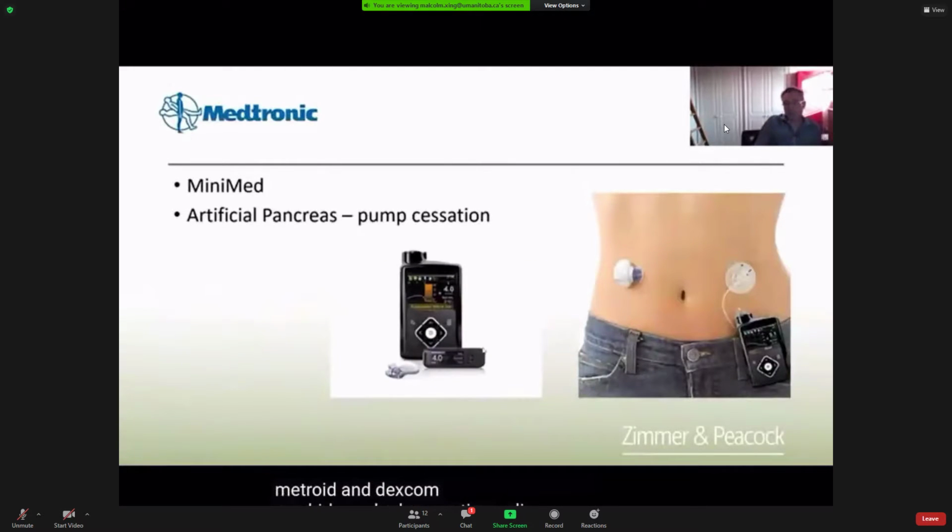So Shirley asked a question online earlier about whether we could measure glucose and deliver insulin in the same patch. That's quite nice because Medtronic have that type of system. They don't have it in the same patch. On the torso here, they're measuring the glucose using a CGM sensor, and then they have a pump delivering insulin. When the sensor controls the insulin, that's called closed loop, and that's called the artificial pancreas. That's the term for it.